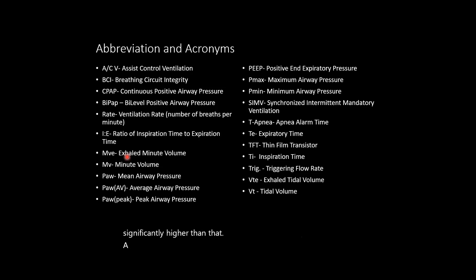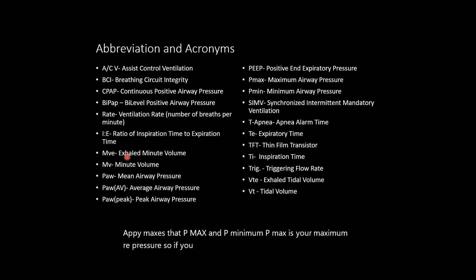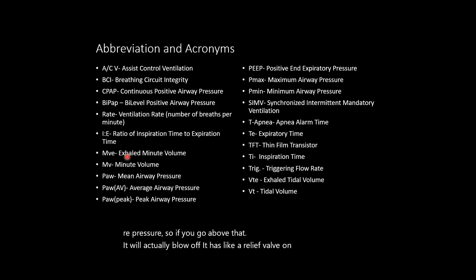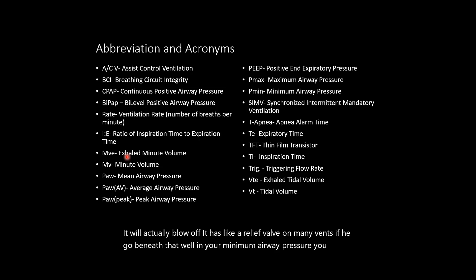Pmax and Pmin. Pmax is your maximum airway pressure. So if you go above that, it will actually blow off. It has like a relief valve on many vents. If you go beneath your minimum airway pressure, you can actually set it on some vents so that you always have at least a minimum push to the breath that you're giving in.